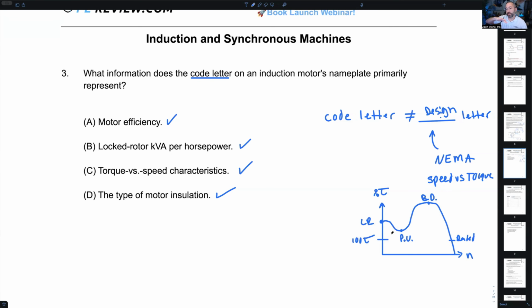Different NEMA motors have different torque characteristics, meaning the torque of a motor is not linear. Oh, I dropped my pen. Hang on. The torque of a motor, we can say, is approximately linear in this region from breakdown to rated. Rated is where we want it to be. It's where it's designed to operate. Everything before then is a roller coaster, right? Linear means straight line.